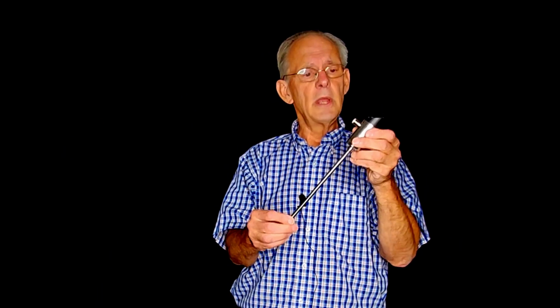Flow sensing. Then we have, this is a flow sensor. Okay, and this is something fairly new. This is a thermal dispersion type of flow meter. So what happens is there's a heat source and there's a temperature sensing element down in here. And this is put into a pipe, and how fast the liquid or air or gas sheds heat determines how fast it's going. So the velocity of the water or air going past the sensor tends to cool the sensor. So that cooling effect is how it judges how fast it's going.